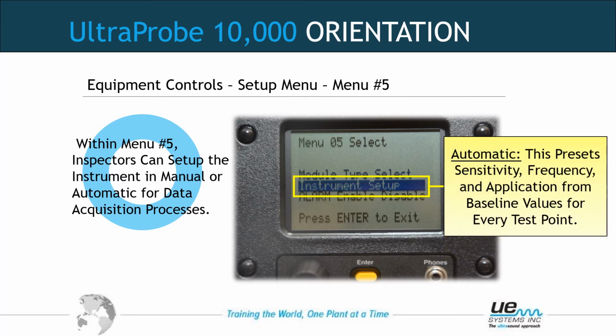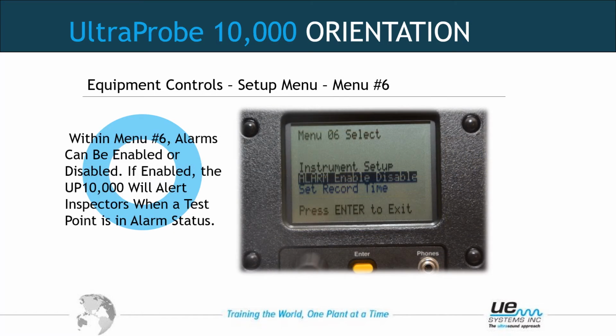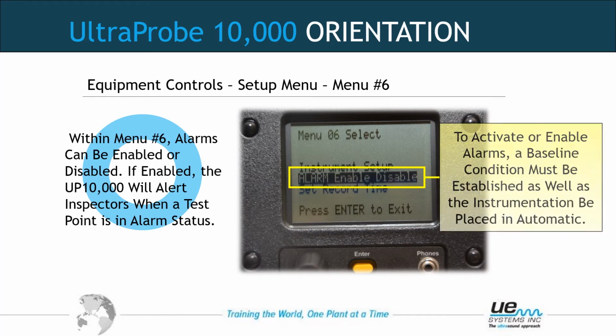Rotate on to menu number 6. Alarm enabled or disabled. If enabled, the 10,000 will alert inspectors with a test point in its alarm status. The headphones will tone and it will flash on the screen that we have gone over an alarm. Typically, this would be used in a bearing route.